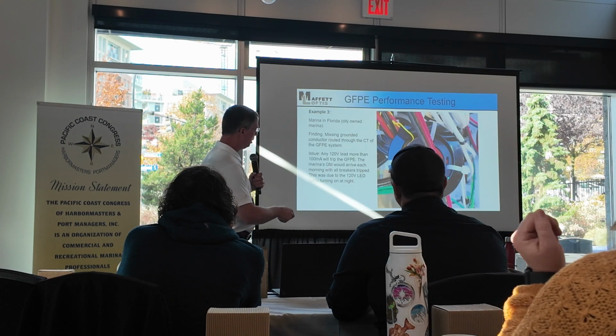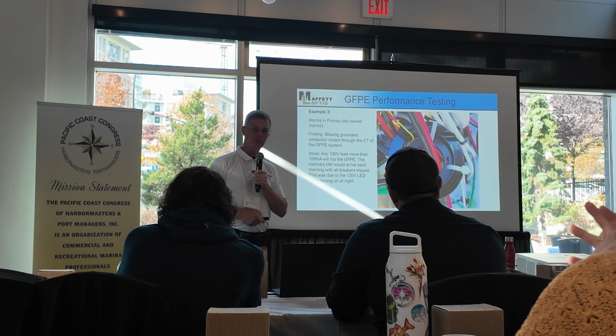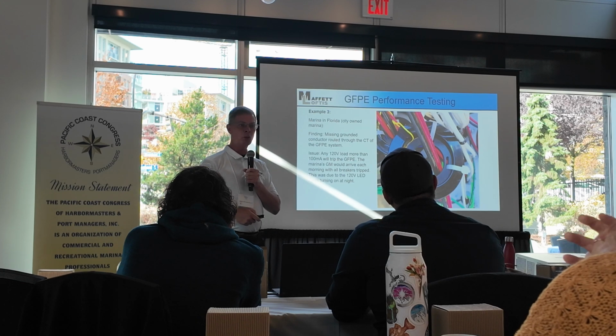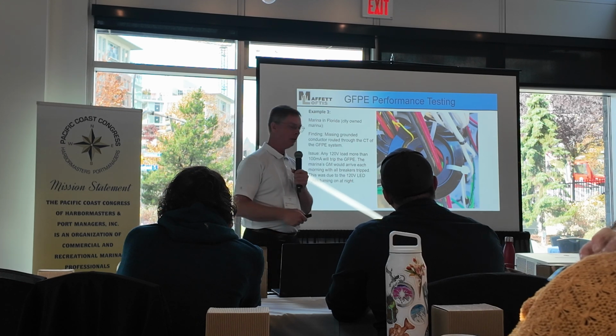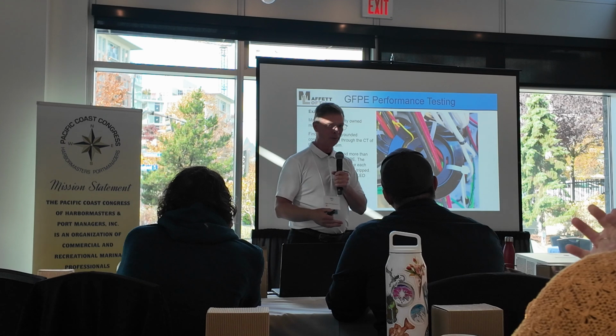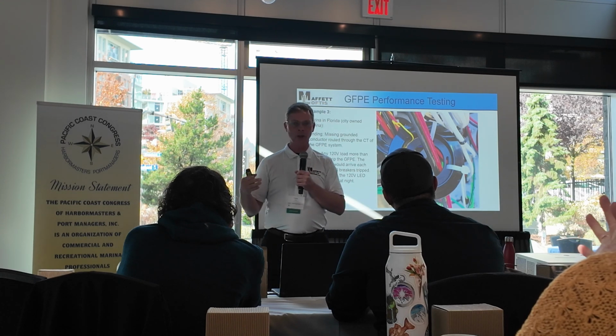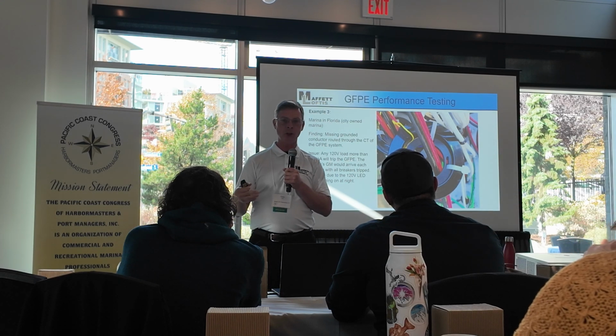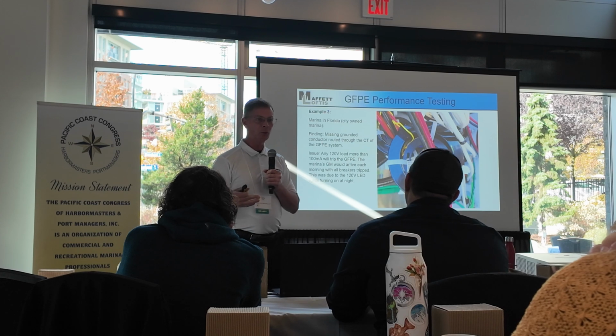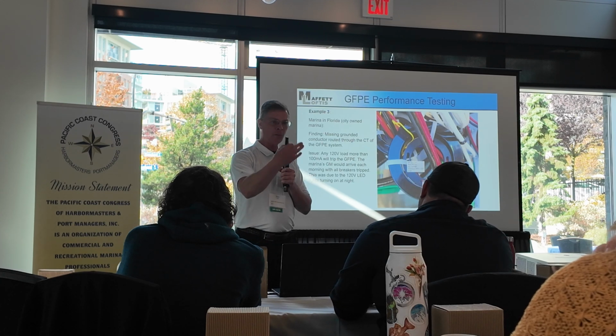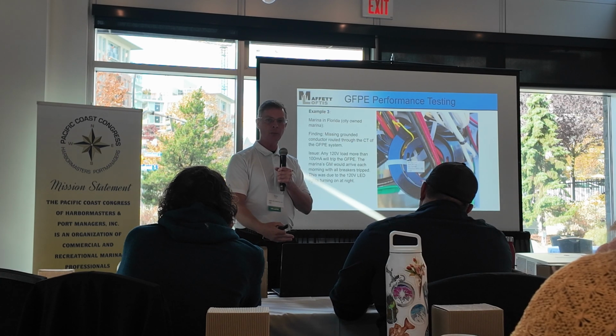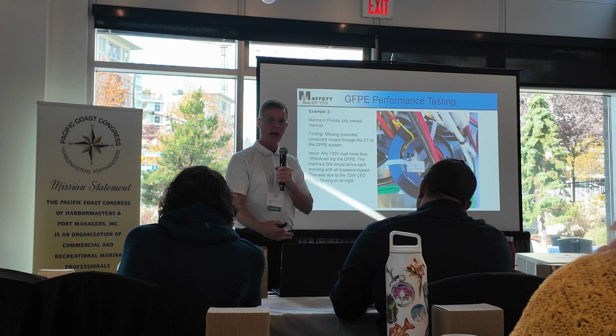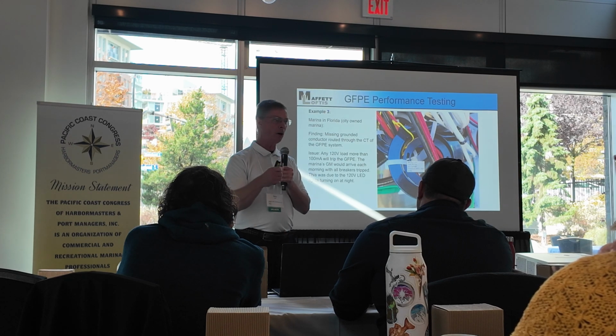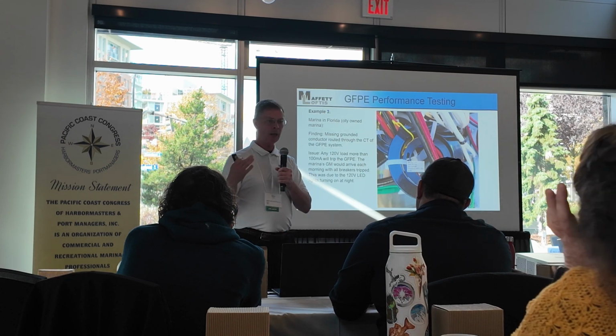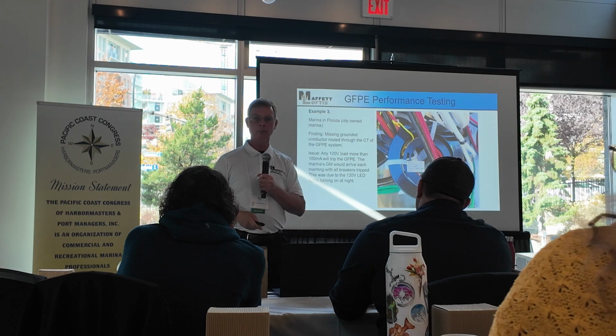Here is another CT, and guess what's missing there? The neutral's not in it. And this was very interesting because the contractor filed for substantial completion. I went out to do the performance testing, and before I started, the contractor said, well, what's wrong with this one substation? Every single GFPE breaker will trip at night. I come back in, I have to reset them all, I start doing my work, then come back the next day, and every breaker's tripped.